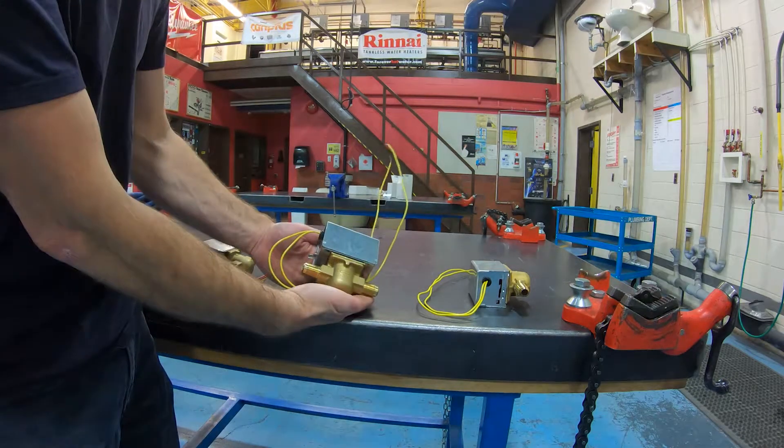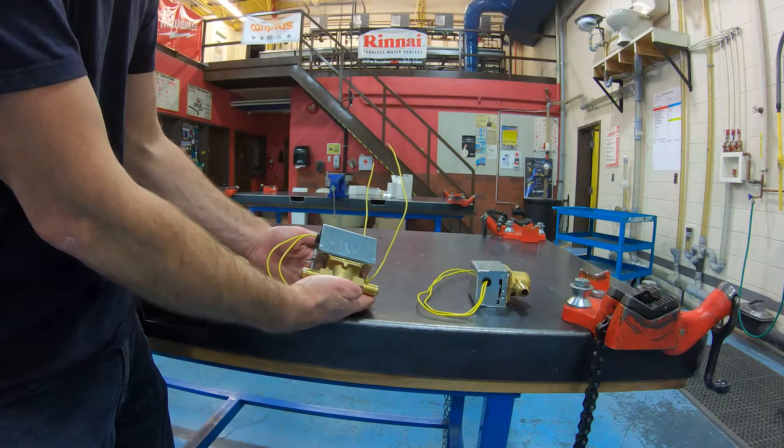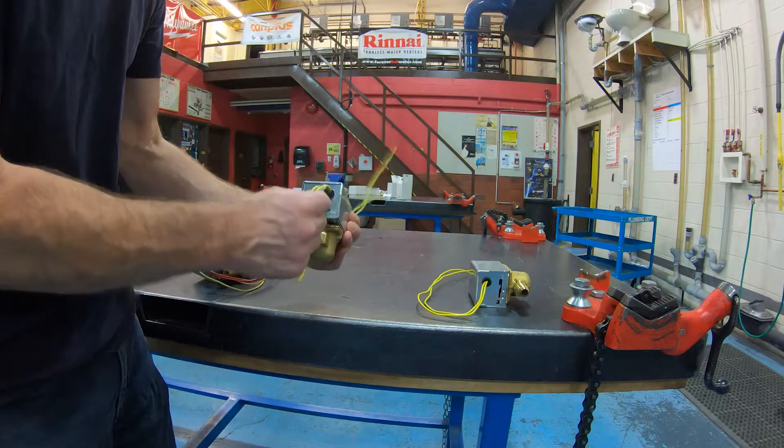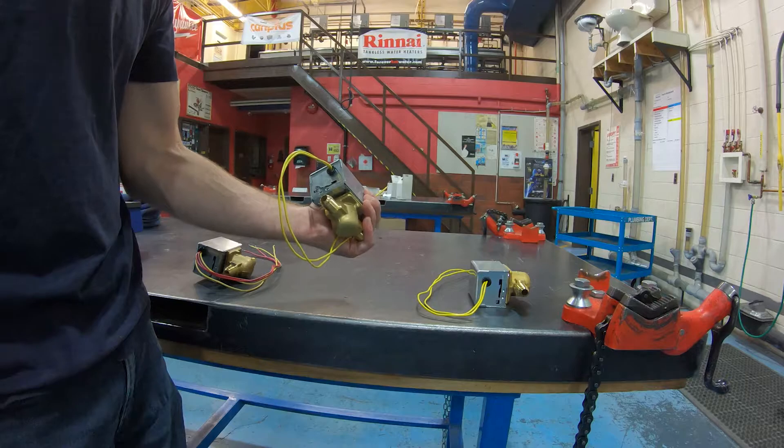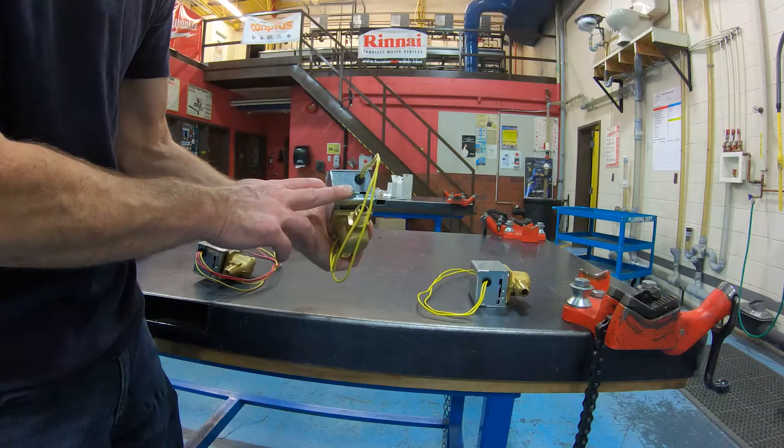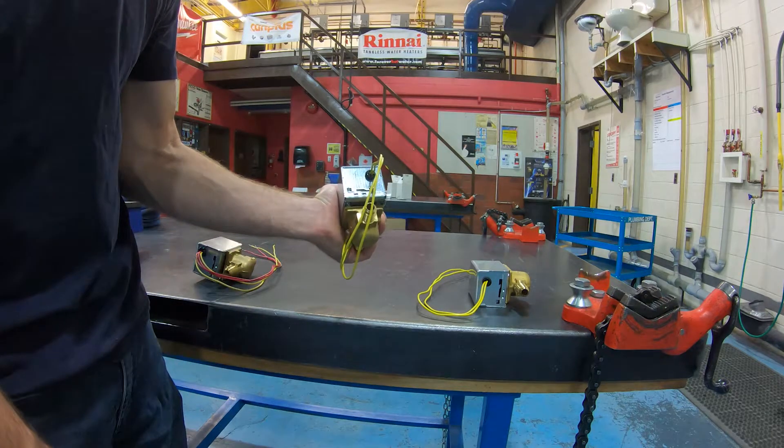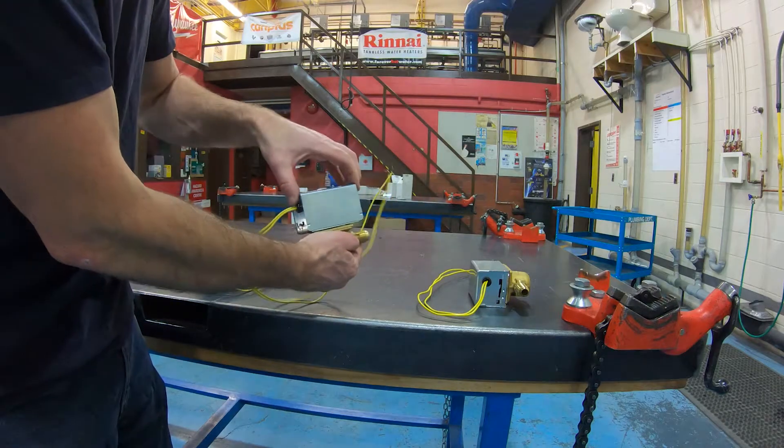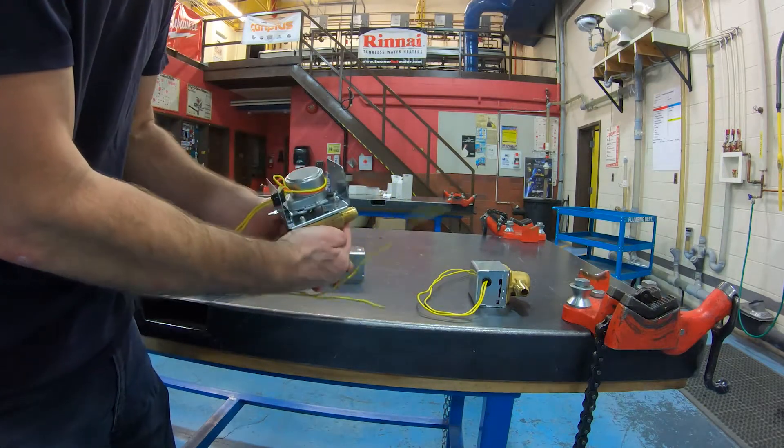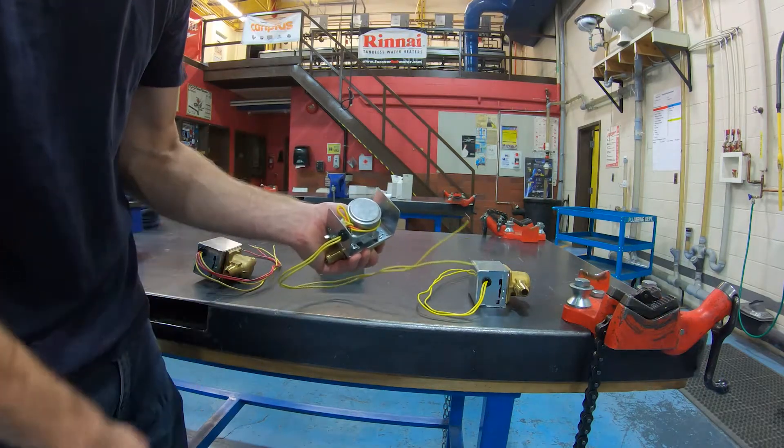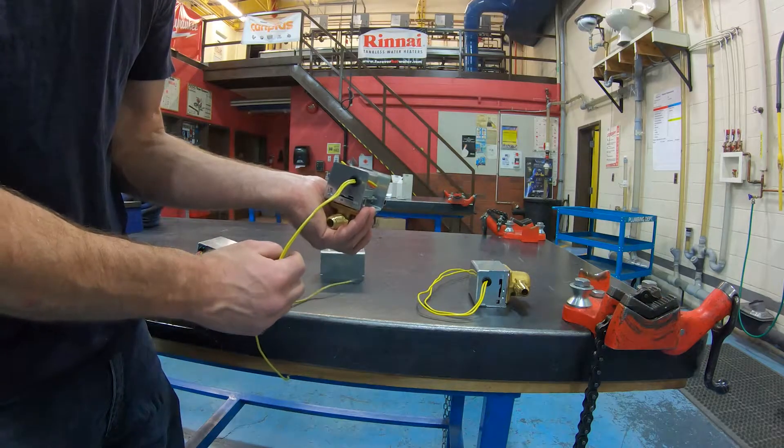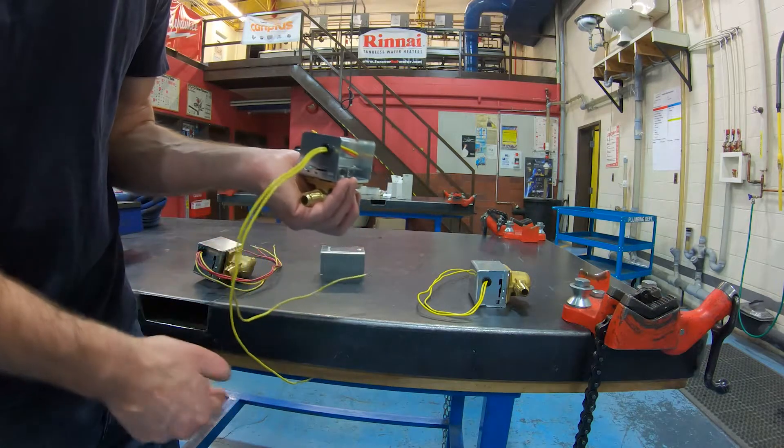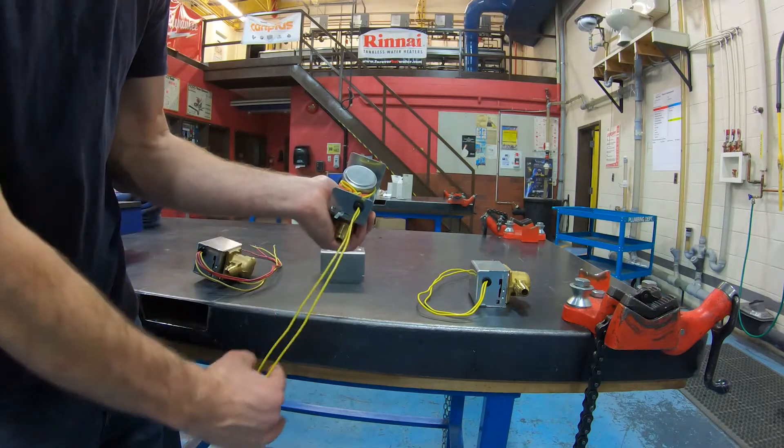The first zone valve type is a normally closed zone valve, that is just plain and simple a zone valve. So this is an electronic valve that starts and stops the flow of water. I can tell it's normally closed because it has a manual tab where I can manually open up the valve. On the inside, the zone valve is going to look pretty similar to all the others. I have a little electric motor, we call that the actuator, and two wires coming in.